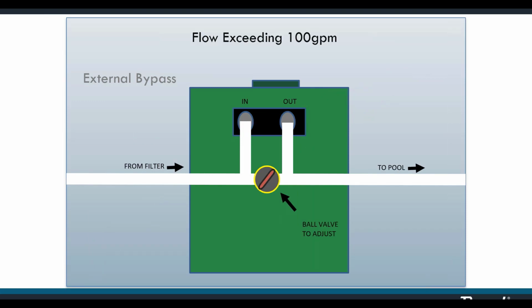Now, here's another configuration for a bypass. If you use this one, the ball valve is on the main line. So in order to push any water at all through the heater, that valve would have to be at least partially closed. Wide open means no water is going through the heater. Completely closed means all the water is flowing through the heater. And again, positioning of the flow meter is important.